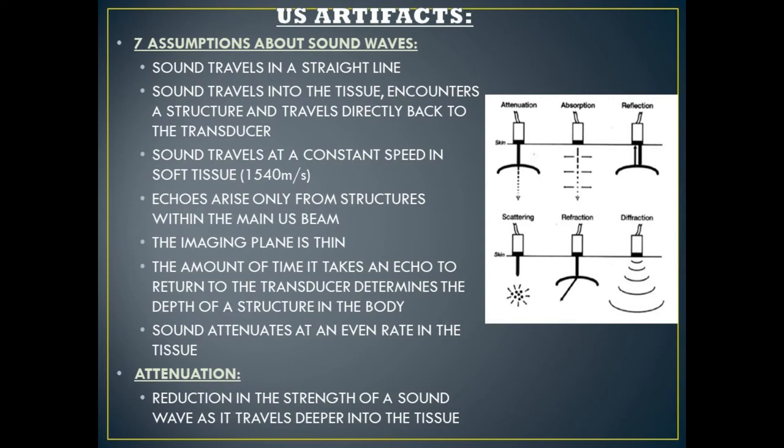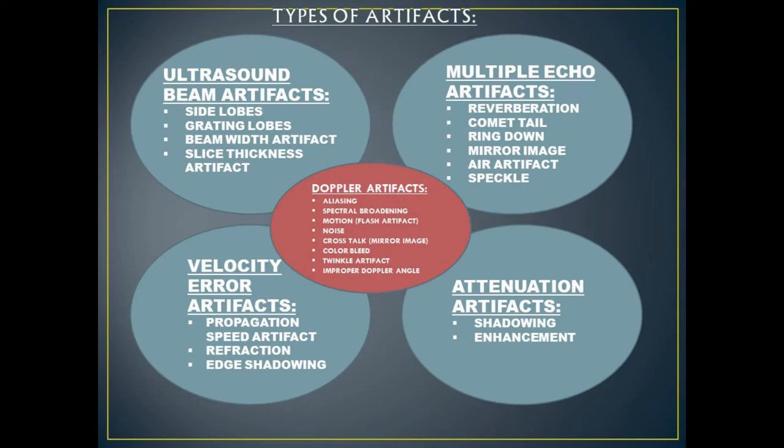When any of these assumptions fails to occur, an ultrasound artifact is formed. Today, we're going to talk about velocity error artifacts. There are five categories of artifacts: ultrasound beam artifacts, multiple echo artifacts, velocity error artifacts, attenuation artifacts, and Doppler artifacts.